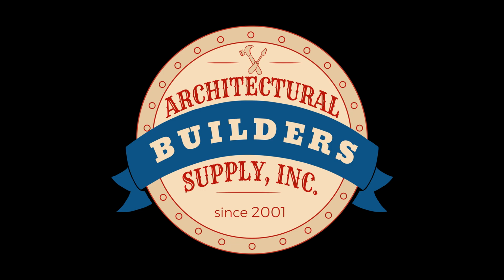So if I order 4 3-by-7-foot doors from you guys that basically have 0 prep on them and have them shipped to me out here in Seattle, will those 4 doors come with the fire-rated sticker? To answer that question, I would say, what hardware will be applied to the door? That's the question. You'll say, the hinges and this weird lock from an elevator. I'll say, then the answer would be no, the door will not have a label on it.